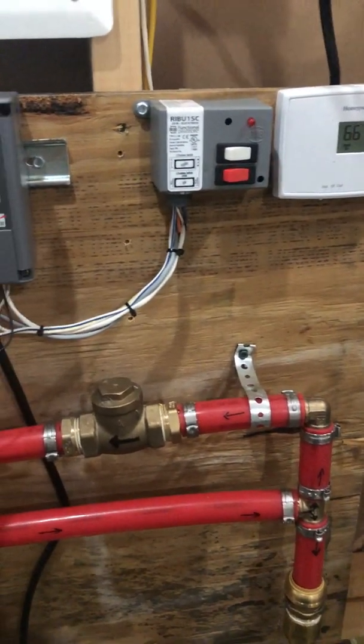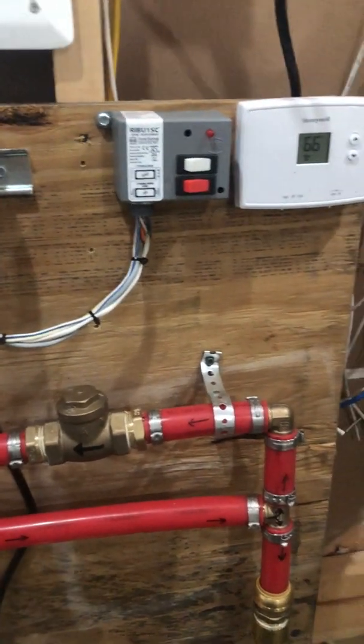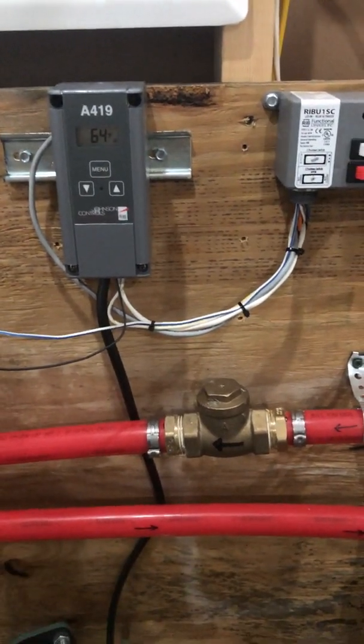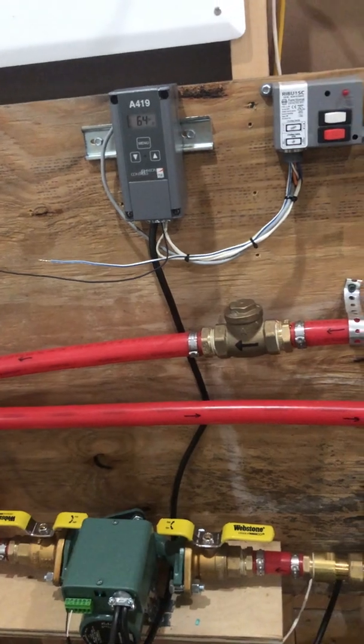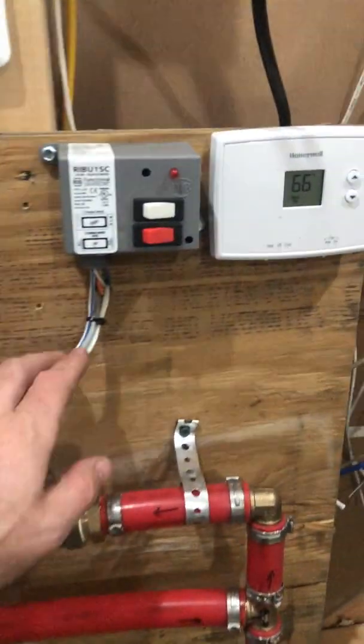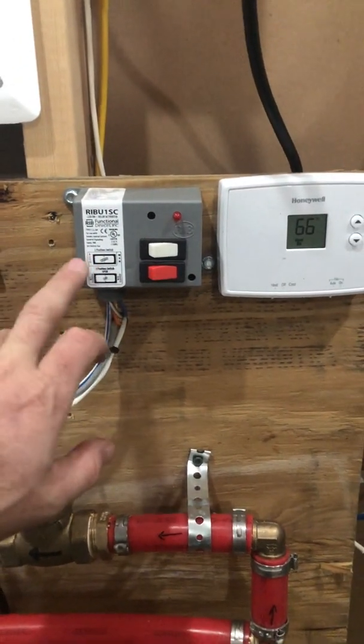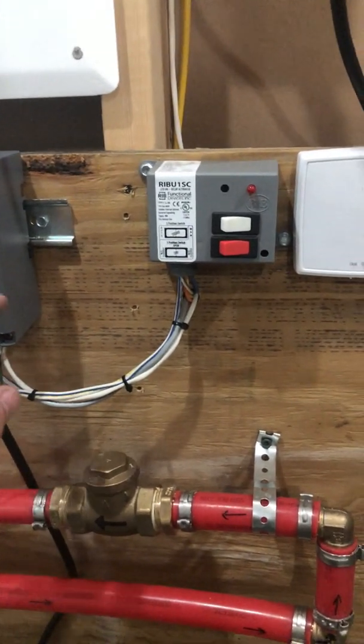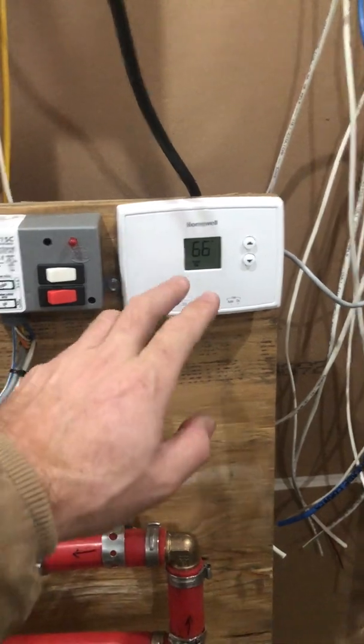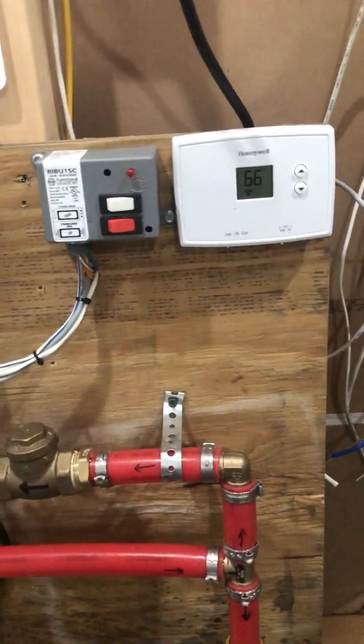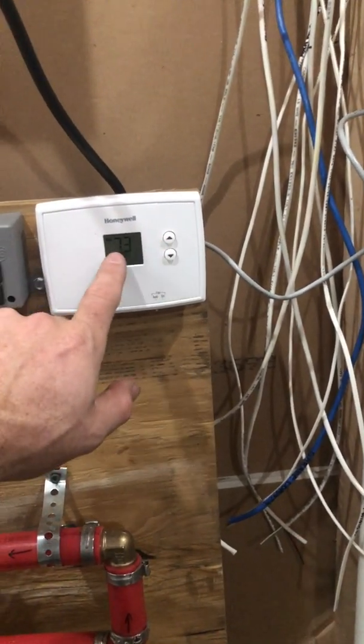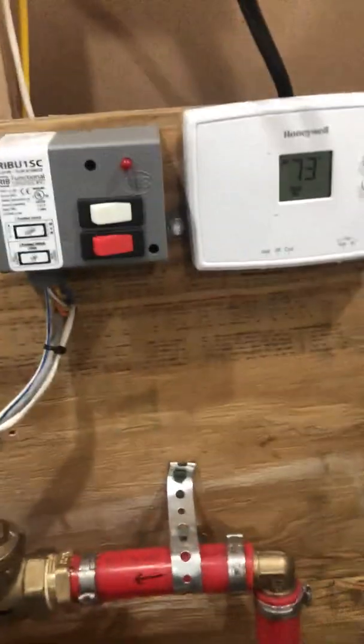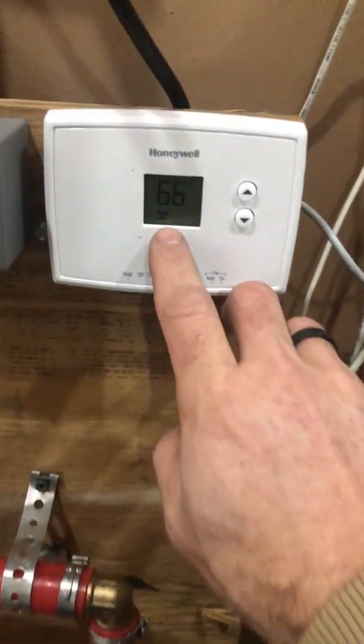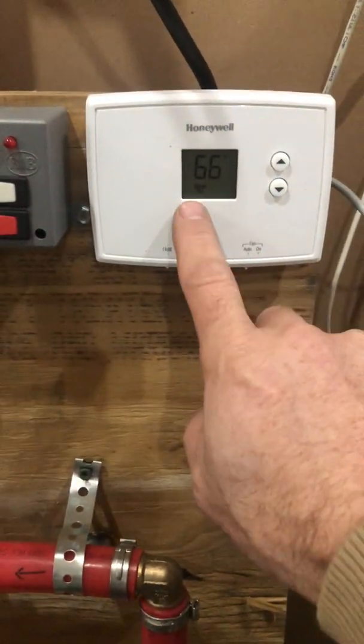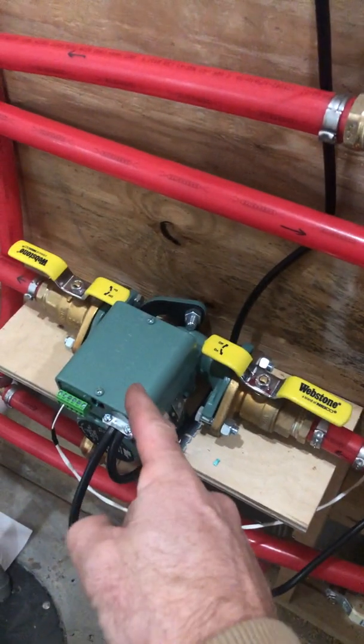So it's just closing a circuit. This is operating a switch. So if my water temperature drops below 100, then what's going to happen is it'll close those circuits and it'll allow my heat pump to function as normal. So I don't have to have two thermostats upstairs. A lot of people will put one thermostat over another, and I chose not to go that route. And then this relay here, I can do it automatically or manual. This is just saying, hey, the water temperature is proper. And so this thermostat here, now, yeah, I know it's a little confusing. It can be. This thermostat here is only for the basement floor. So right now it's 66 degrees in here, but I've got it set on, let's say, 73. So at 73 degrees, this is not satisfied. So you'll see it says heat is on. So when this thermostat is not satisfied, it's turning my circulation pump to the floor on.